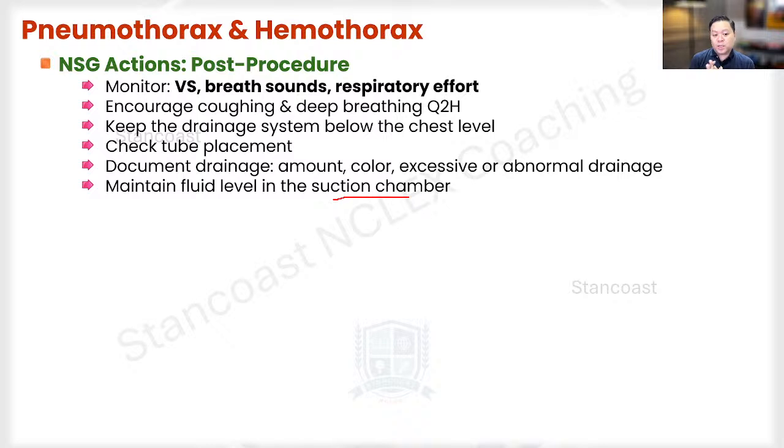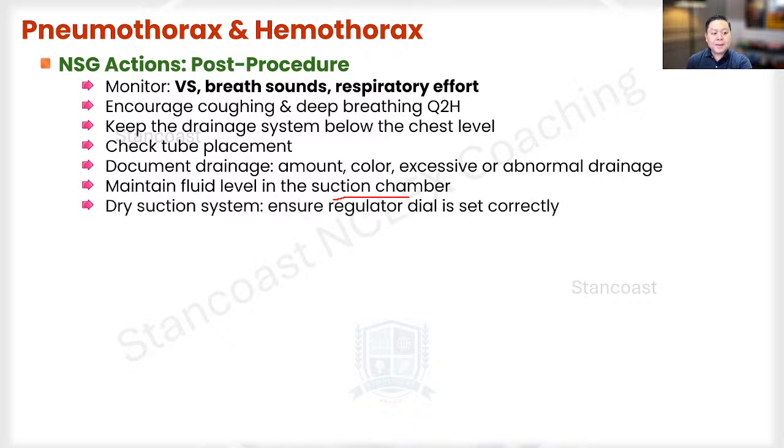And another thing that you need to pay attention to is the maintenance of the fluid level in the suction chamber. Why? Well, because if there is a suction that is applied to the system itself, this can cause rapid evaporation of the fluid in that chamber. Okay? And this will lead to some more problems later on if we're not going to replenish the level. So we're going to talk a little bit more of that later. And with the dry suction, because there's two different setups here.